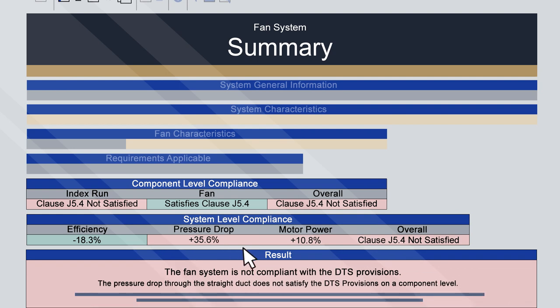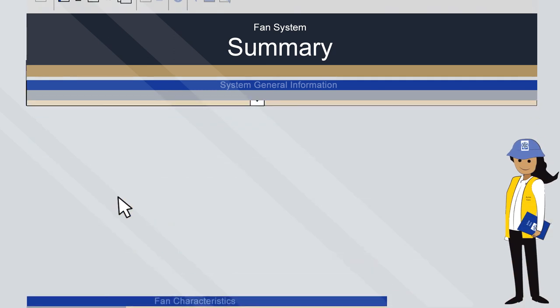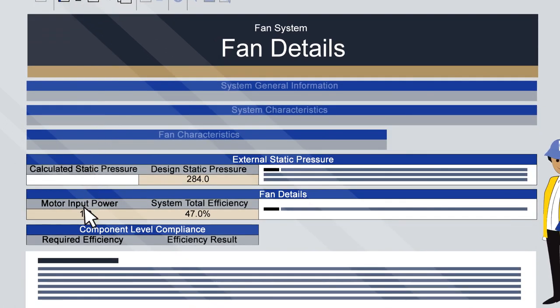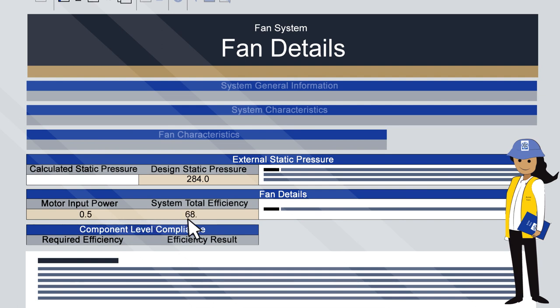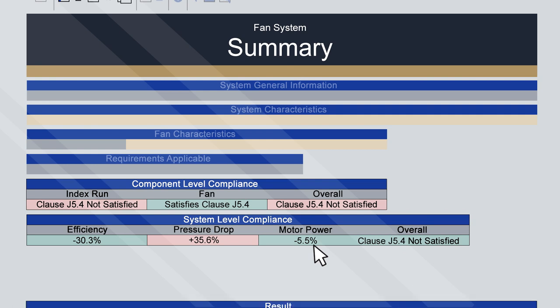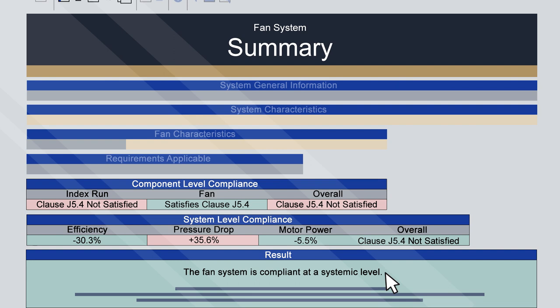Suggested ways to achieve this are shown in the results section. Alternatively, a different assessment method could be considered. Let's look at improving the energy efficiency with a more efficient fan, or changing the specifications of the ducts to provide a system that satisfies Clause J5.4. Using a different fan: first, update the information on the Summary sheet to specify a centrifugal backward curved fan. Returning to the Fan Details sheet, update the motor input power and system efficiency. Returning to the Summary sheet, it now shows the efficiency of this new fan is sufficient to offset the pressure drop of the index run, and reduces the required motor power to an appropriate level. Therefore, the fan system now satisfies Clause J5.4 at a system level.